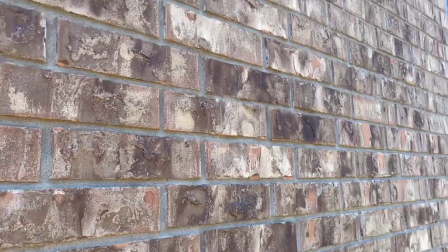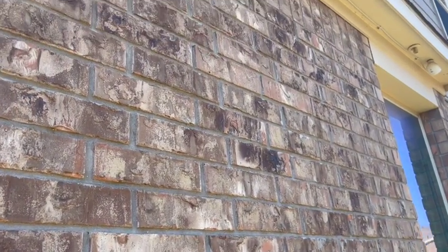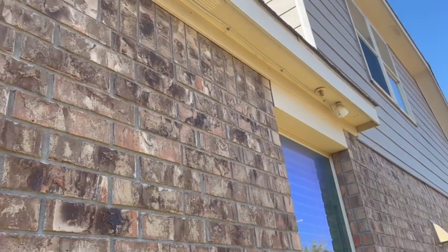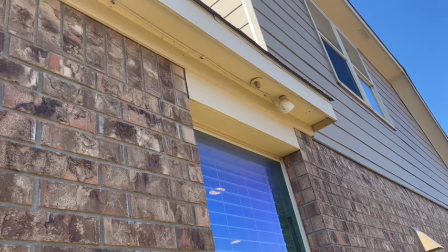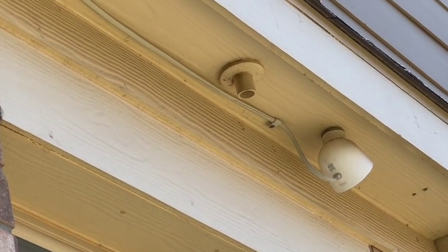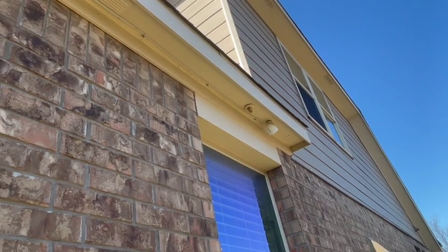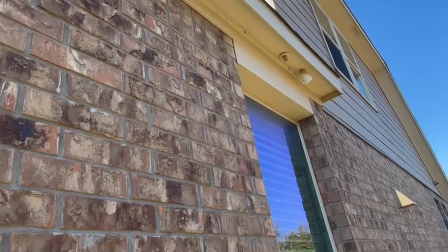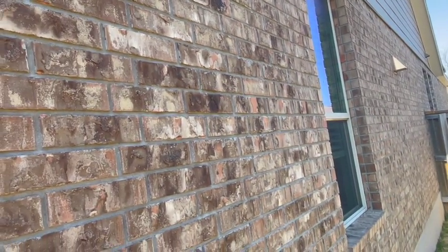When we take a look on the exterior of the house from the perspective of where we saw that drain line going from the attic, we can see over this window here we have a piece of PVC sticking down, and that is going to be the actual secondary condensation line. So this is the conspicuous location that the builder has chosen for this house to place that line.